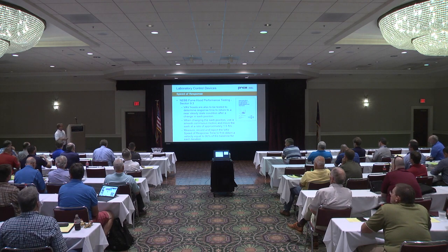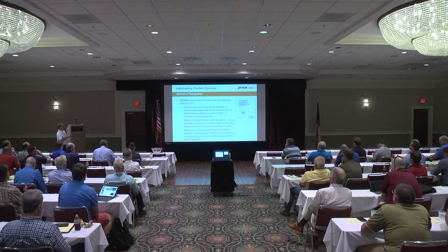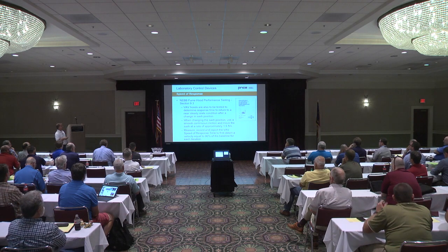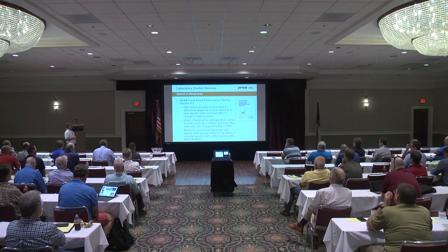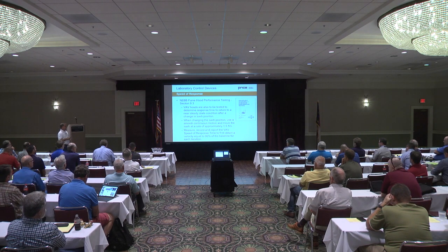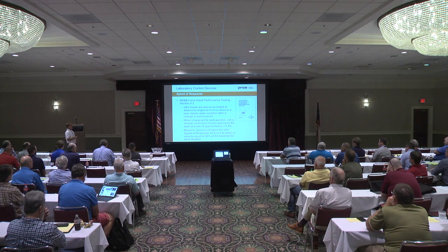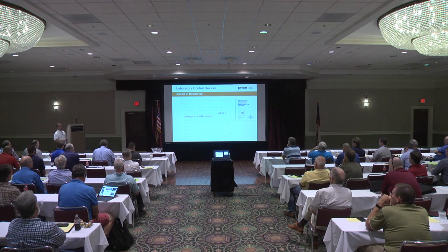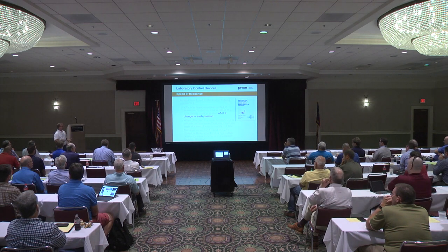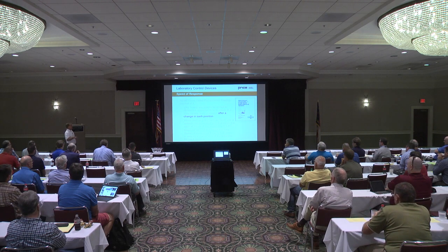So in VAV fume hood testing procedures, look at there, an NEBB document. VAV hoods are also to be tested to determine response time to return to near steady state condition after change in sash position. When changing sash position with smooth continuous motion, measure, record, and report the VAV speed of response time to first obtain a velocity equal to 90% of the baseline for each iteration. So this is right out of the NEBB standard for fume hood testing. But the part that's important here is after change in sash position. So after the sash has started to move is when these measurements need to be recorded.